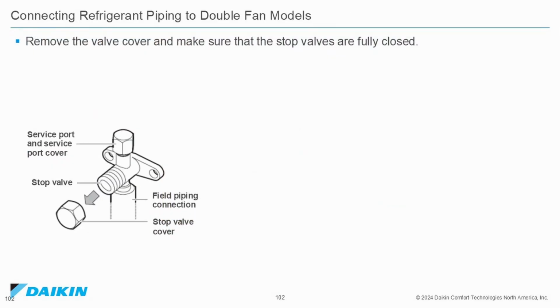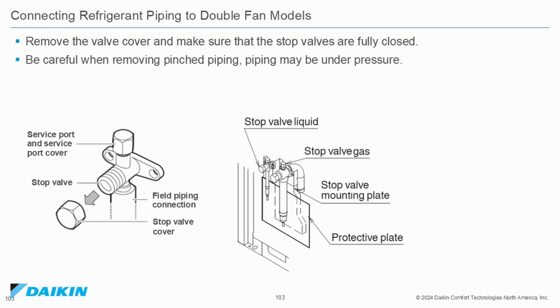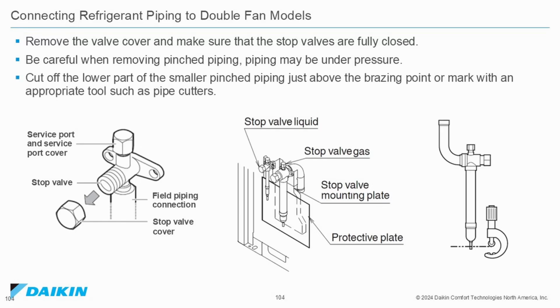Remove the valve cover and make sure that the stop valves are fully closed. Be careful when removing pinched piping. Piping may be under pressure. Cut off the lower part of the smaller pinched piping just above the braze point, or mark it with an appropriate tool such as pipe cutters.